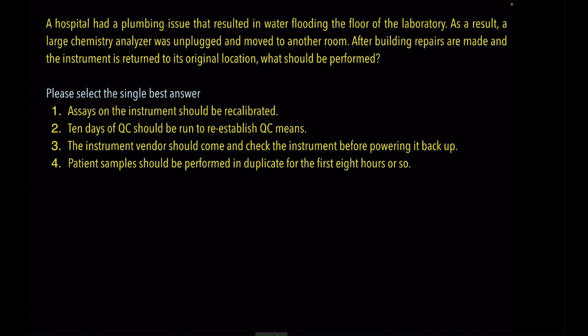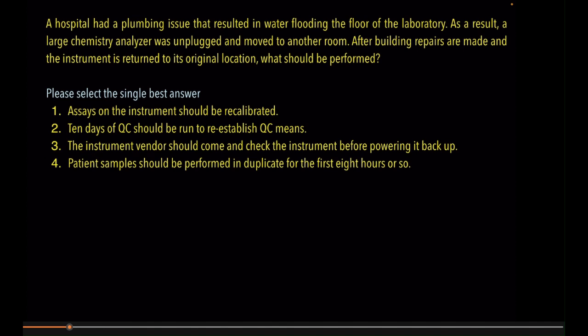1. Assays on the instrument should be recalibrated. 2. 10 days of QC should be run to re-establish QC means. 3. The instrument vendor should come and check the instrument before powering it back up. 4. Patient samples should be performed in duplicate for the first 8 hours or so.